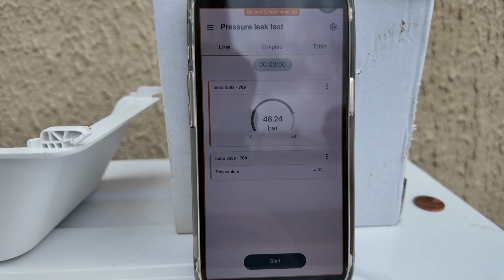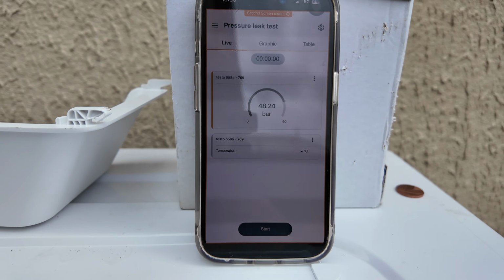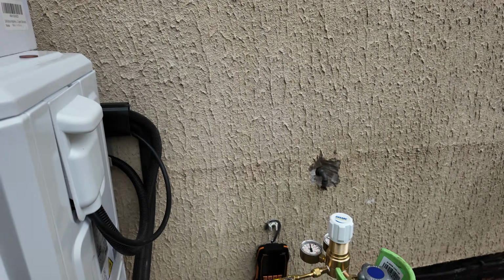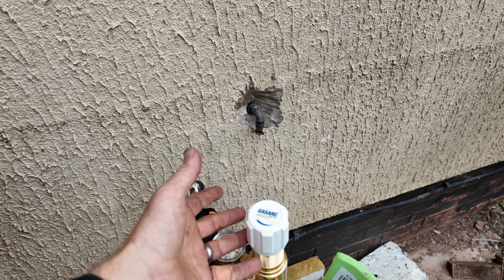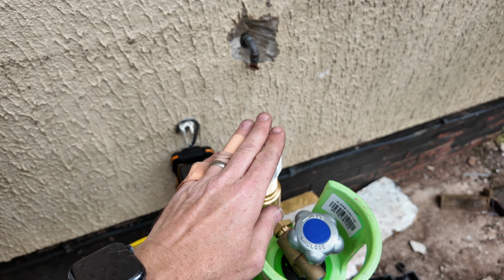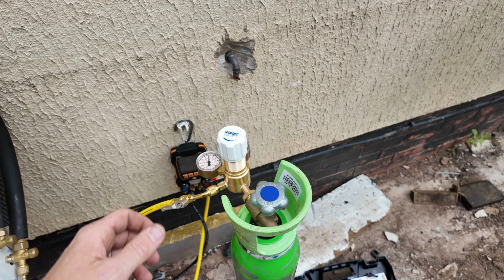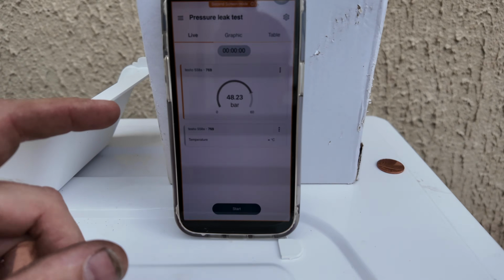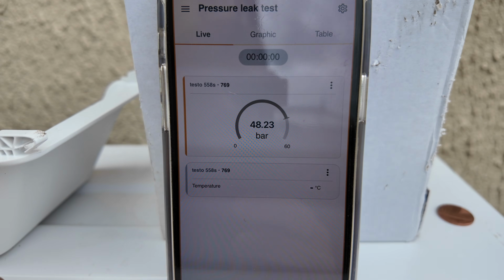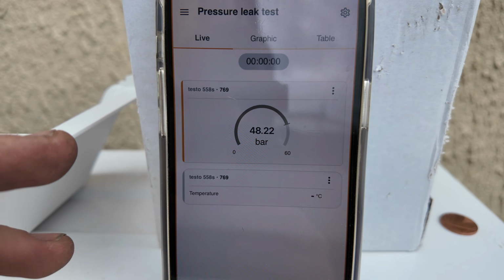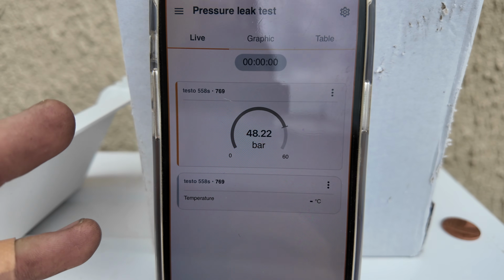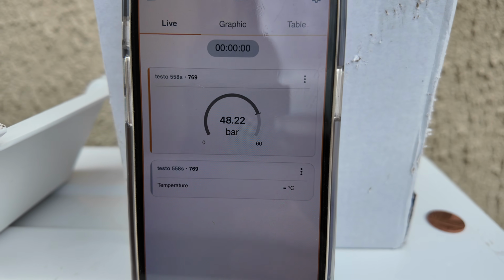That's the first test you do to make sure all your pipes and joints are okay. What we'd recommend is don't go hell for leather opening that - just do it in increments, don't just whack it open. You can see now it's at 48 bar. We're going to let that rest now and just make sure it doesn't drop. Let it stabilise, make sure it doesn't drop.